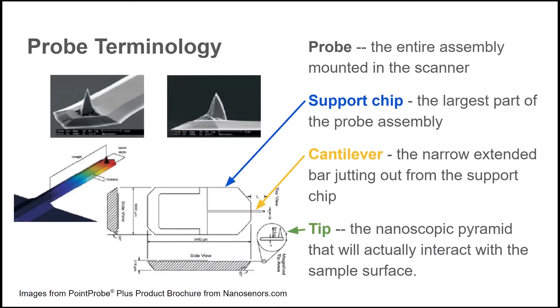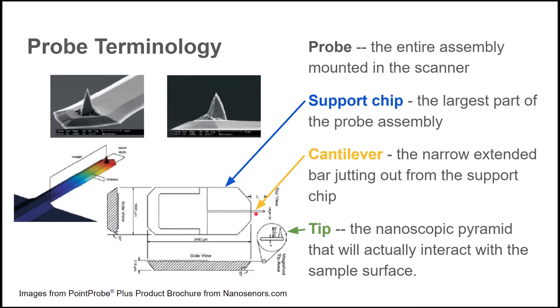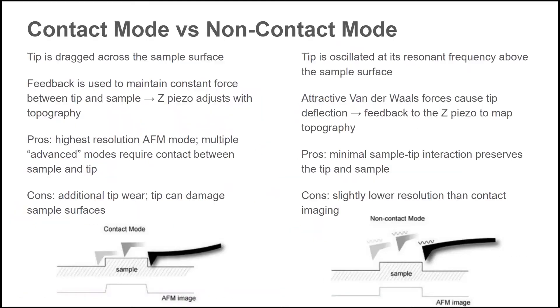Your job is to make sure the laser signal is correctly aligned on the probe and PSPD. The AFM probe is probably the single most important component in an AFM measurement. Probe refers to the entire assembly. The support chip is the largest part of the probe assembly. The cantilever is the narrow bar jutting out, and the tip is the actual part of the probe that touches the sample. Note in this SEM image that the tip is not at the very end of the cantilever.